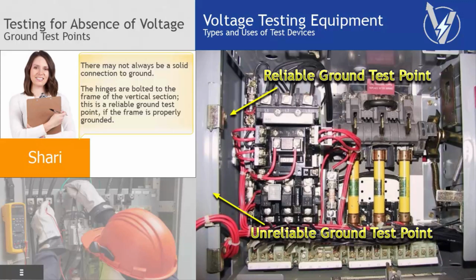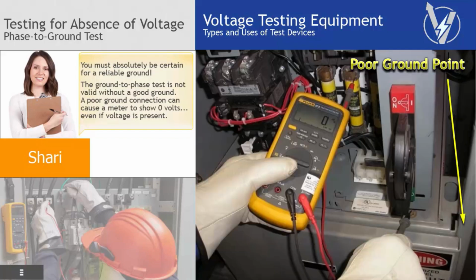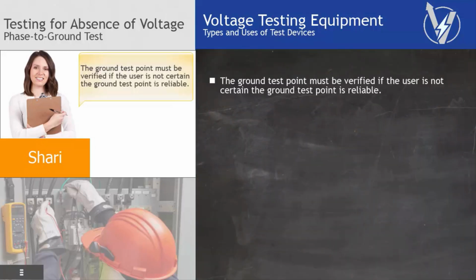There may not always be a solid connection to ground. The hinges are bolted to the frame of the vertical section. This is a reliable ground test point if the frame is properly grounded. You must absolutely be certain for a reliable ground. The ground-to-phase test is not valid without a good ground. A poor ground connection can cause a meter to show 0 volts, even if voltage is present. The ground test point must be verified if the user is not certain the ground test point is reliable.